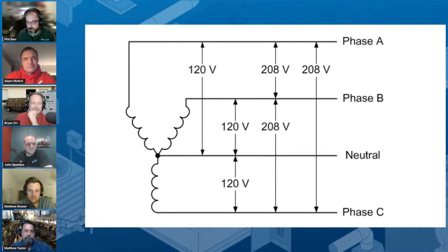I usually think of phase balancing from the perspective of what's returning on the neutral. If your phases are balanced — if you have 10 amps on A, B, and C — you'll end up with zero amps returning on neutral, because they balance each other out. It's mathematical; it's just how it works.